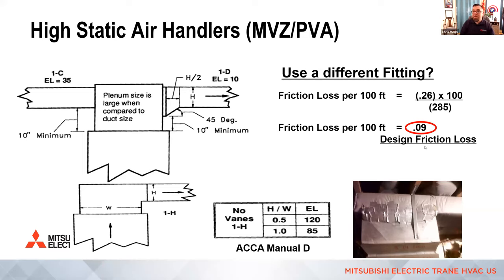A couple questions came in. Since the shortest equivalent length runs will have an actual friction loss higher than the longest equivalent length run, why doesn't calculating just for the longest run get into trouble with the other runs? That, Lee, is because we have balancing dampers and we can balance the duct system out. So if we can't get the air to the longest run, then we're going to have a comfort problem. So we always want to make sure we design around the longest and then we balance the system. That's the last step. If we don't balance, we could then run into other problems.